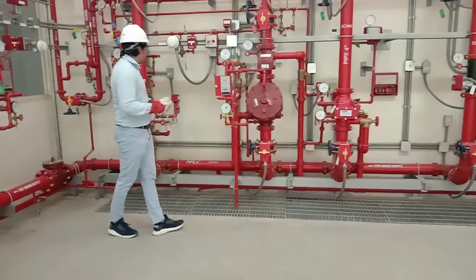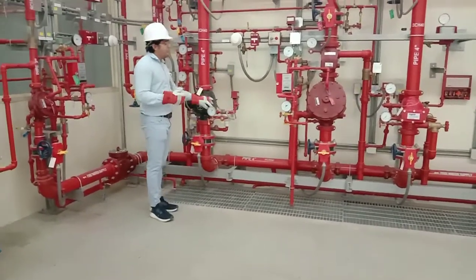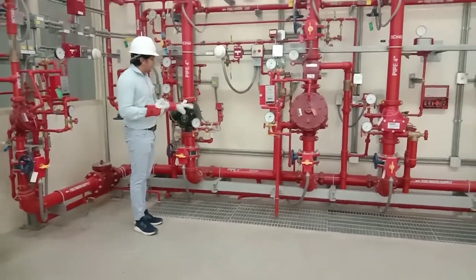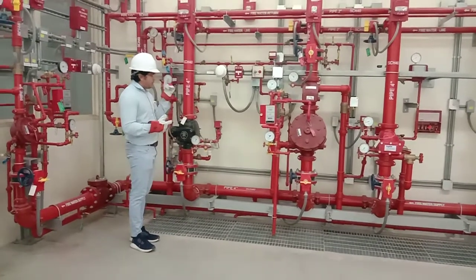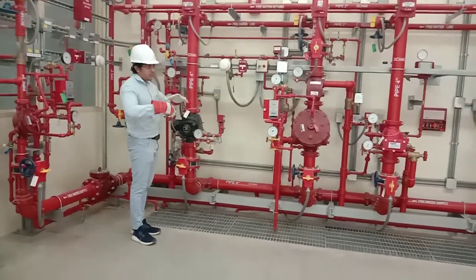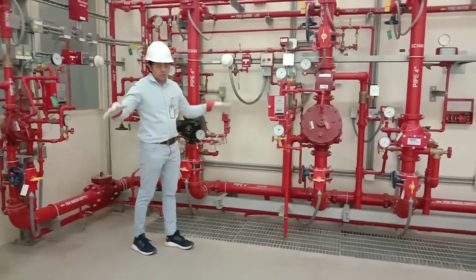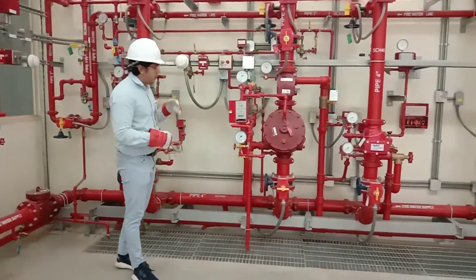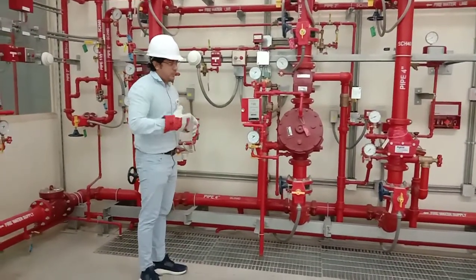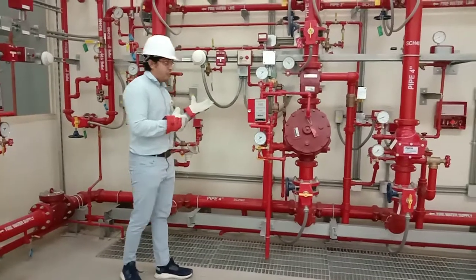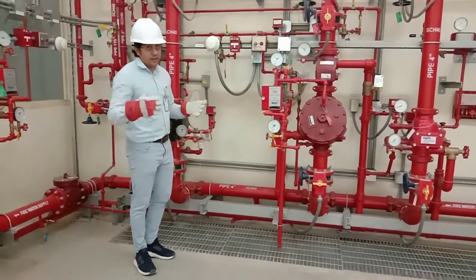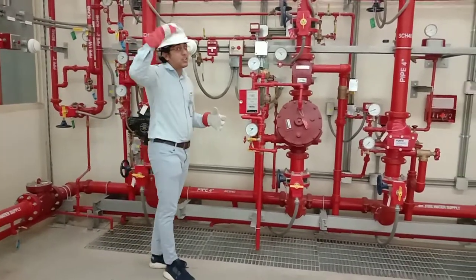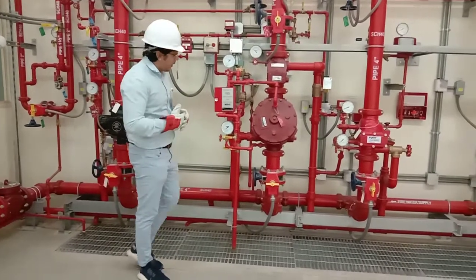The next one we have is the deluge valve, right? Deluge means flood. We discussed a lot regarding the deluge valve, and the sprinklers are open. When there is a fire, water will discharge into the complete room, and it will flood the room within a short period of time. I mean, it's protected. It's intended for high-challenge fires where the heat release is exponential, like power plants and all.